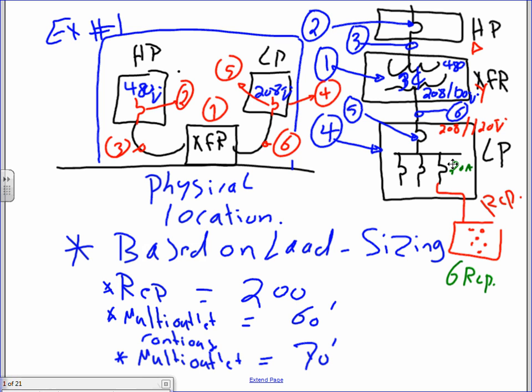Everybody knows why we care, because in every building that you walk in, you're going to size these. Remember when we started dropping the receptacles, building our riser, and you asked me what size transformer do I need for the receptacle balance? You had to pick this. Well, based on what? Based on this calculation. Unfortunately, we haven't done the calculation. Now we're going to go back and review. Actually, we're going to size that transformer for our project as one of our examples. You'll see. So if your size is different, all you have to do is go put the right size. Okay. Any comments, gentlemen? Any questions? Everybody's cool with that?